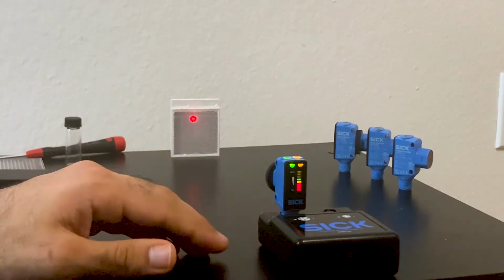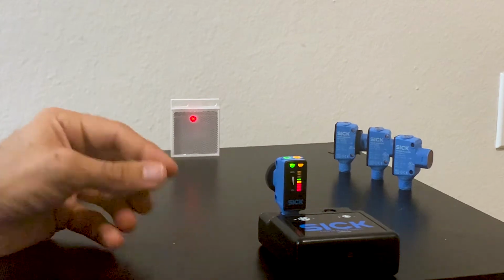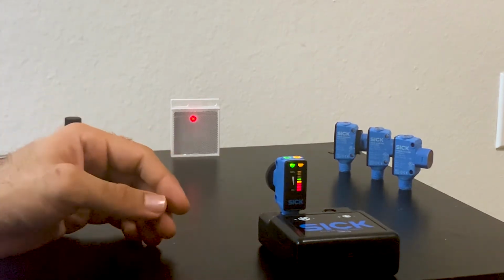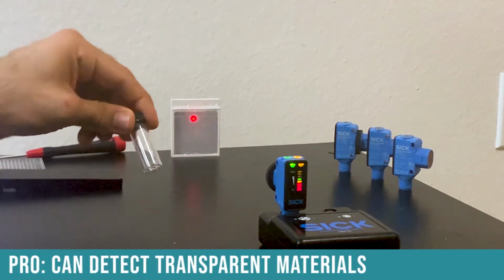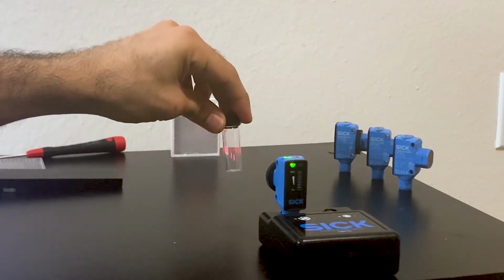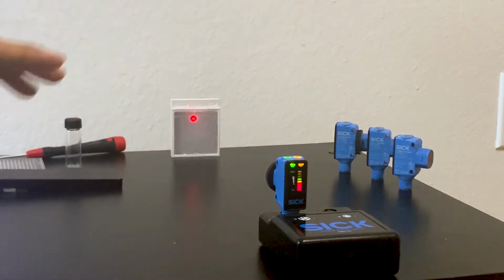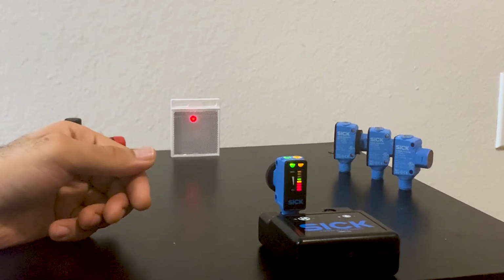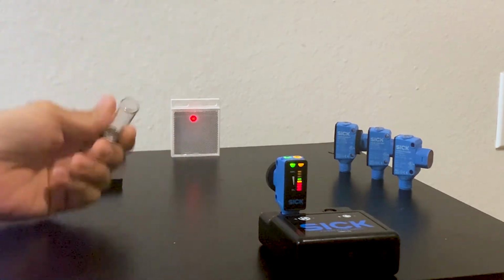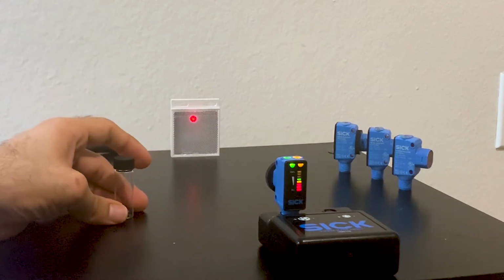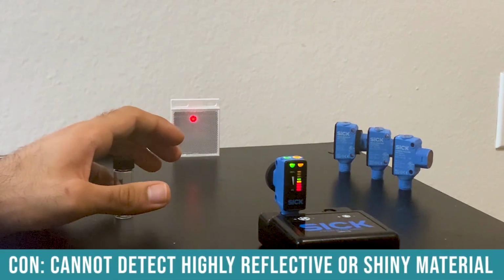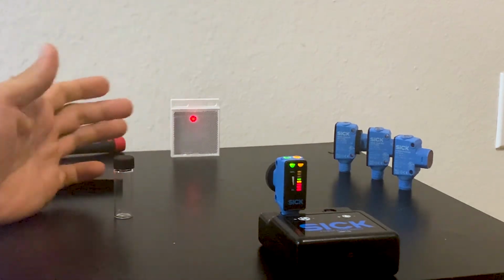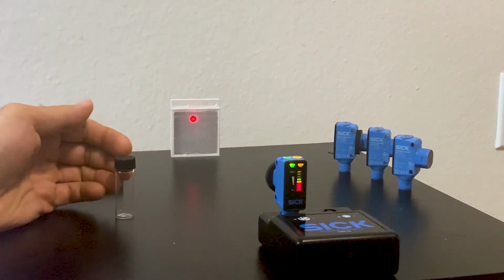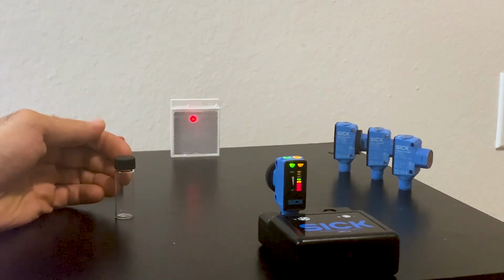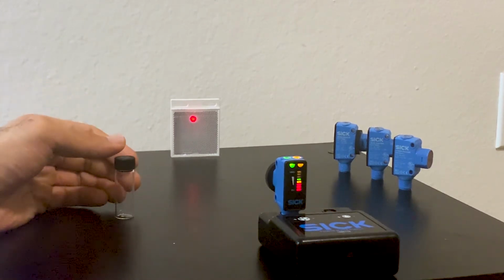These sensors also have autocollimation technology, which allows them to see small parts. The biggest pro of these sensors is that you can use them to detect transparent materials very effectively, and you'll find the majority of packaging industries and manufacturing units that deal with glass or plastics use these retroreflective sensors. The biggest con is that you cannot detect highly reflective or shiny materials, because they end up false triggering the sensor, making it think it's actually the reflector itself. But SICK also makes polarized reflective sensors, which are able to ignore that and detect very reliably.